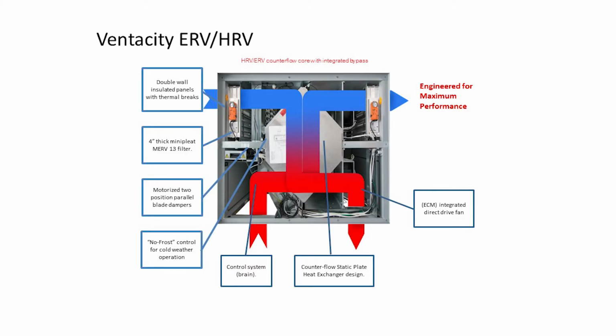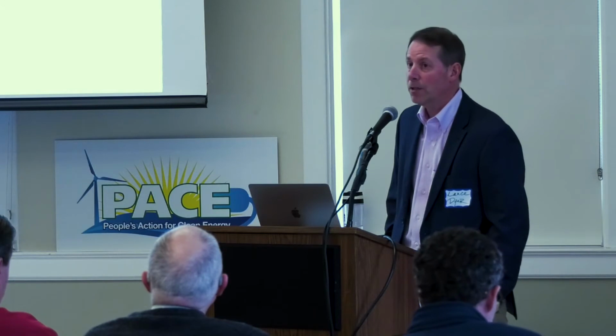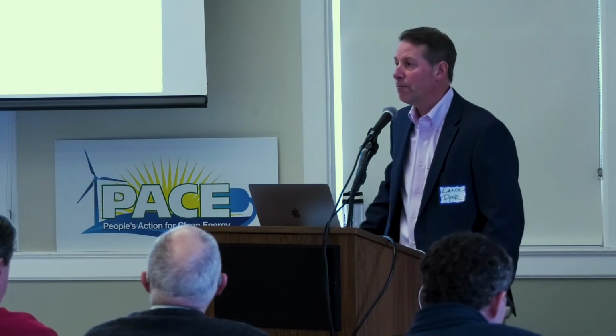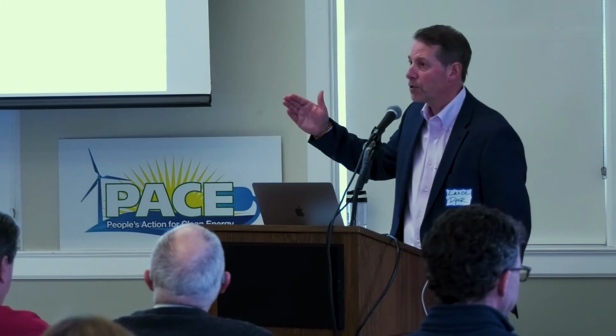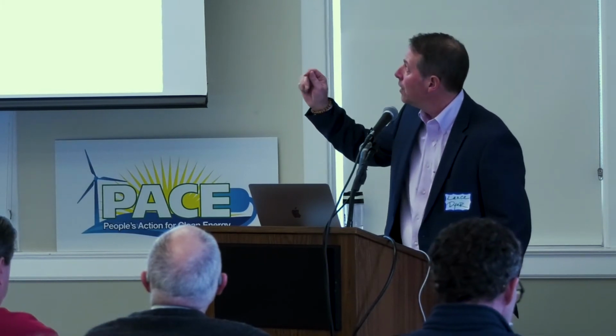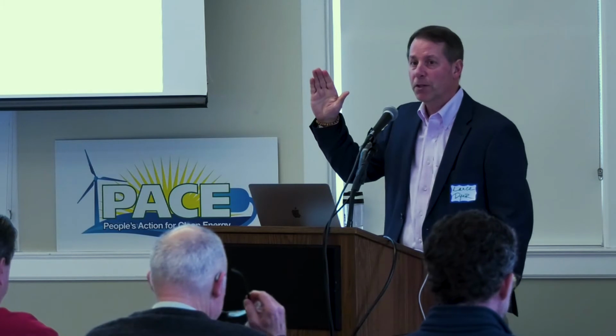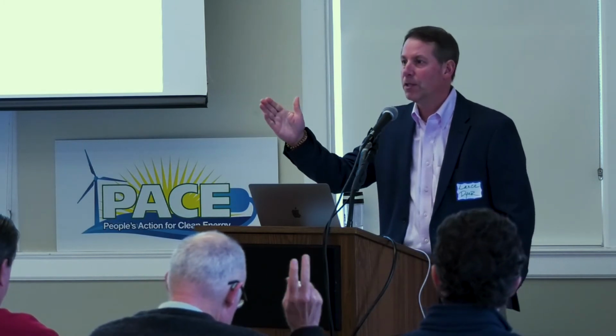Lastly, Ventacity is the ERV, HRV line, energy recovery ventilator or heat recovery ventilator. The difference really between the two and how you choose which one would be right for the application really depends upon the occupancy and also whether or not you need to recover humidity. The heat exchangers in these units are a little bit different between the ERV and the HRV. And I want to preface that so you understand, because as we get into further slides, you'll understand the differences. But the ERV, anybody familiar with the Gore-Tex material? Probably have seen it in jackets and things like that.